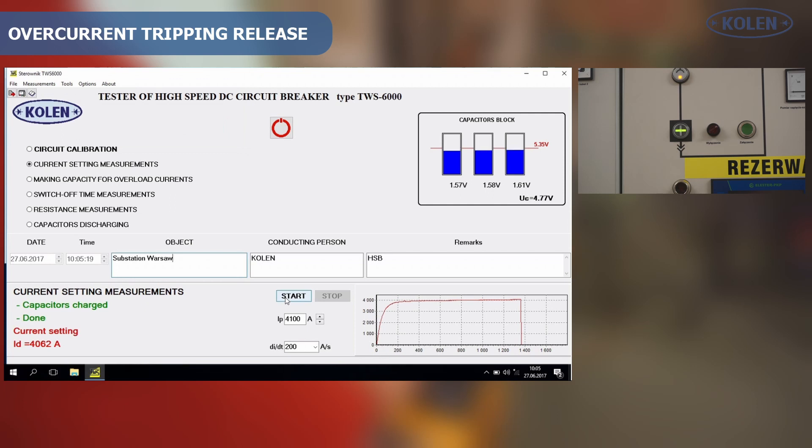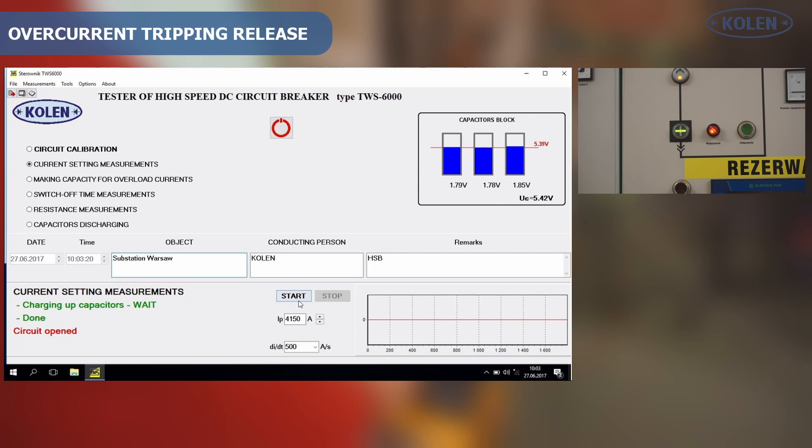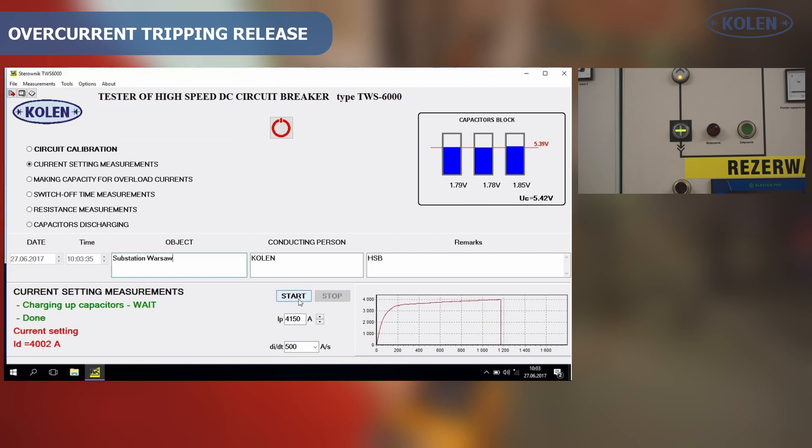The probing pulse duration can be adjusted up to 2 seconds. Overcurrent tripping release adjustment of HSB under test is the maximum probing current value just before opening main contacts.